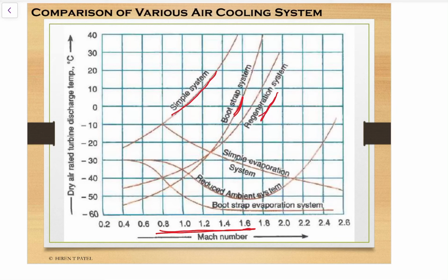One method of overcoming the drawback of the bootstrap system is to use part of the work derived from the turbine to drive a fan which pulls air over the secondary heat exchanger, as we discussed earlier - the power obtained from the cooling turbine is utilized for running the cooling fan, which produces a suction effect inside the heat exchanger, so an induced draft is produced.